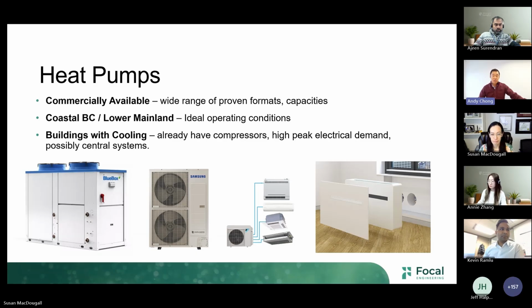They're all different. Coastal BC, and I'd still count Langley in coastal BC, is prime for heat pumps—it doesn't get that cold. We hear grievances about heat pumps stopping at -15, but we have so few hours in this climate zone that actually touch that range. If we're applying our systems correctly and doing good due diligence in engineering, air source heat pumps—if we're going to use them anywhere in Canada—we live in the utopia for them.